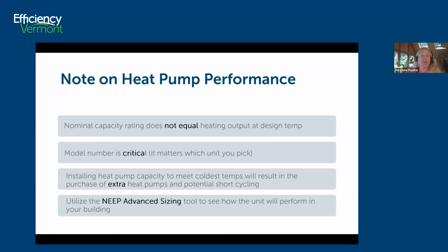And a pitch for the NEEP advanced sizing tool. NEEP is the database of all the approved Efficiency Vermont approved cold climate heat pumps. And they have an advanced sizing tool, which is a different presentation that we've done, and it's worth taking a look at. It shows you how much your unit is going to be short cycling and how well it matches the load of your building.